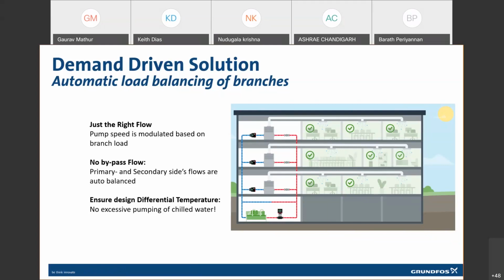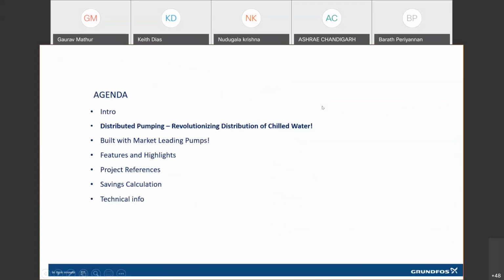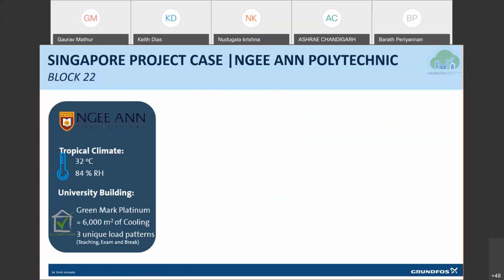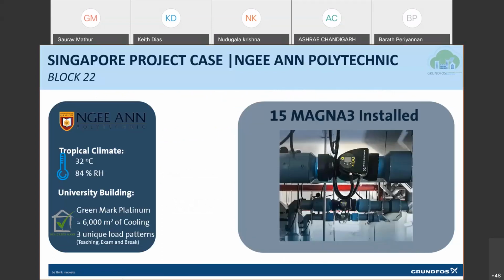What is the indirect way? When you have a temperature signal going to a flow restricting device like a flow modulating valve, and when the valve closes, it is a pressure reading which the pump actually takes and based on which it modulates. That is a way in which we do a control which is indirect. But here you have a direct temperature-based control happening for the pump. And that is what makes it a demand-driven system and automatic load balancing of each of the branches at any load condition. Now let us go deeper into it and see one of the examples where we have implemented this particular distributed pumping project in Singapore.